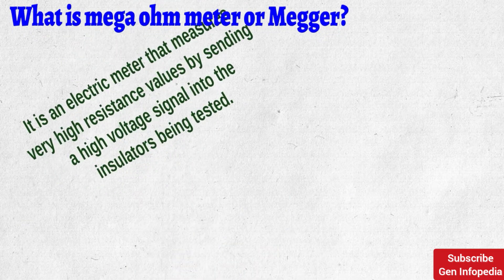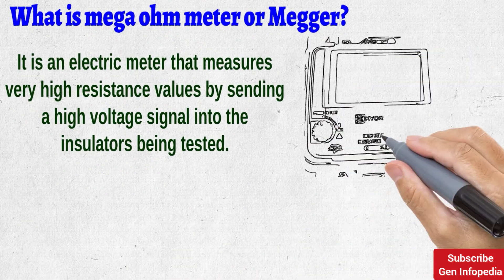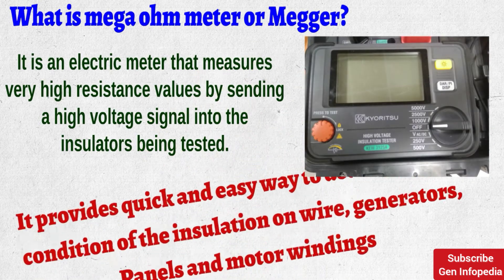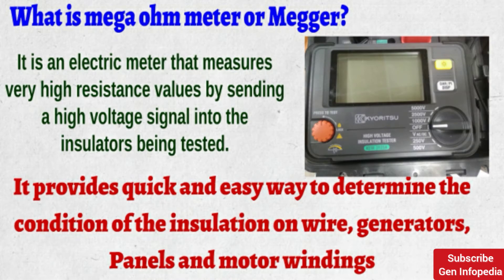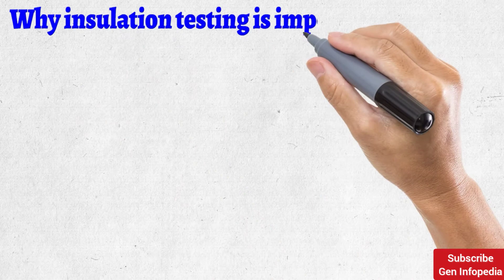A megaohmmeter is an electric meter that measures very high resistance values by sending a high voltage signal into the insulators, providing a quick and easy way to determine the condition of the insulation on wires, generators, motor windings, and transformer windings. This megaohmmeter has a built-in direct current generator — when making an insulation resistance test, a high DC voltage is applied to the conductor under test and the resulting current flow is measured.